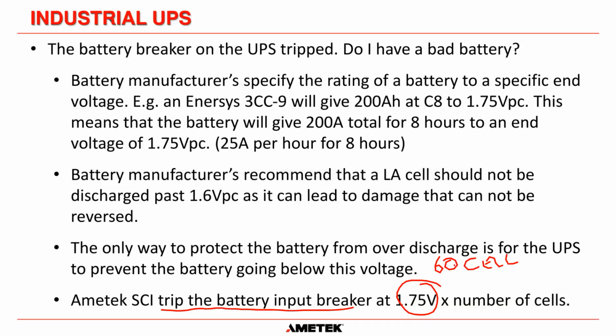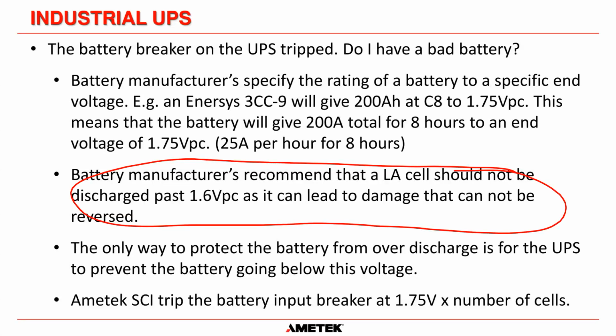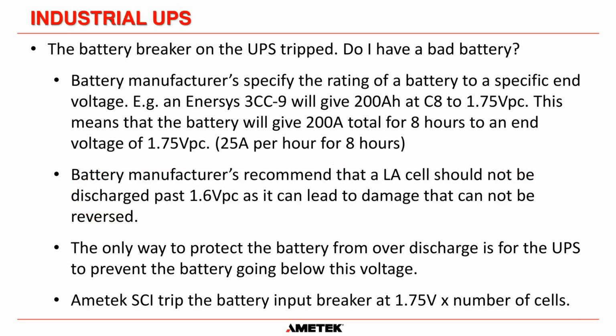And if you multiply 60 by 1.75, you get a total of 105 volts. And that's the voltage that I've been mentioning in the previous slides throughout the presentation. So when the DC bus gets to 105 volts, the AMETEK SCI UPS will transfer the system to bypass, and then it will trip the battery input breaker to prevent the batteries from going below this 1.6 volts per cell, which can cause irreparable damage to the battery. And the batteries are very expensive, so we want to protect them from being over discharged and needing replaced.